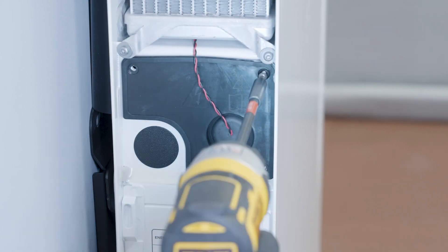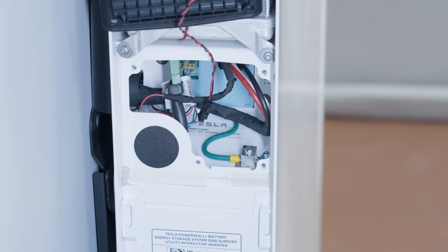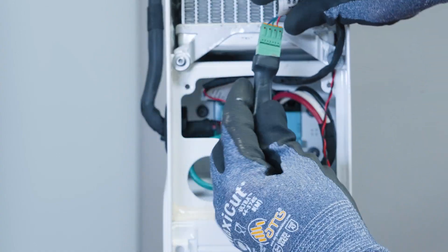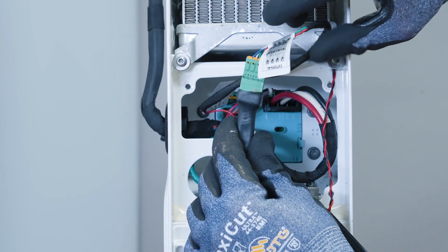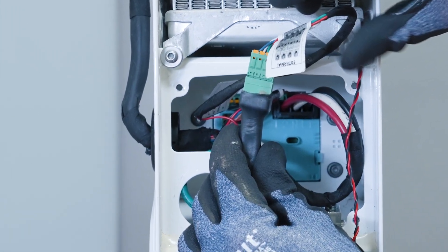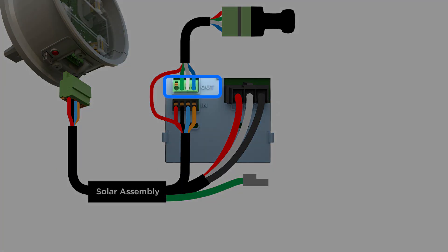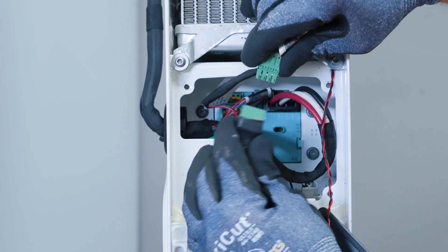Open the battery assembly wiring compartment. Locate the harness with the black shrink wrap. This will be the point of connection for the communication wiring to any additional Powerwalls. Never unplug the connector that is in the out port of Powerwall Plus. Unplug the loose end with the shrink wrap.